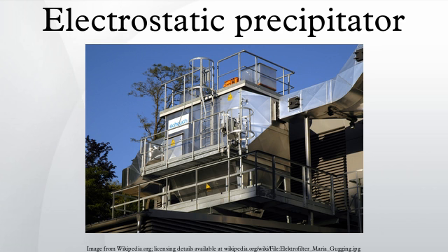Plate precipitator. The most basic precipitator contains a row of thin vertical wires, followed by a stack of large flat metal plates oriented vertically, with the plates typically spaced about 1 cm to 18 cm apart, depending on the application. The air or gas stream flows horizontally through the spaces between the wires, and then passes through the stack of plates. A negative voltage of several thousand volts is applied between wire and plate. If the applied voltage is high enough, an electric corona discharge ionizes the gas around the electrodes.